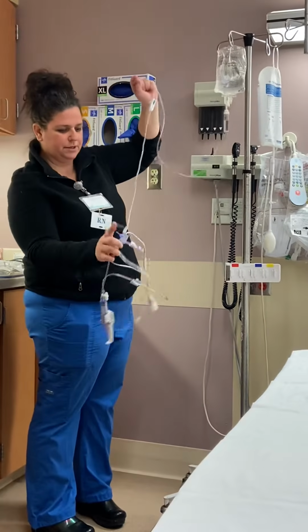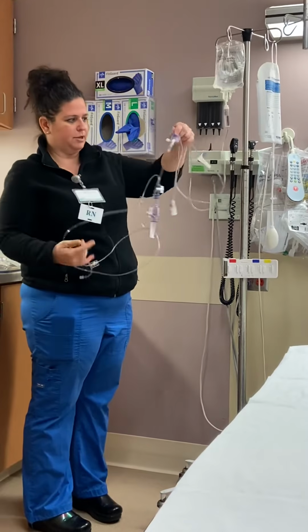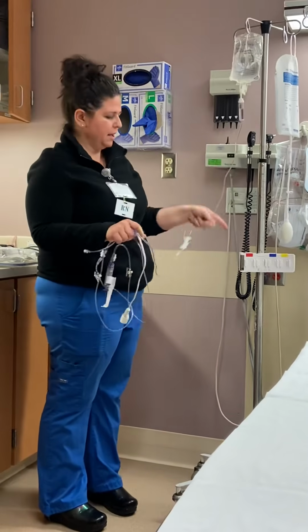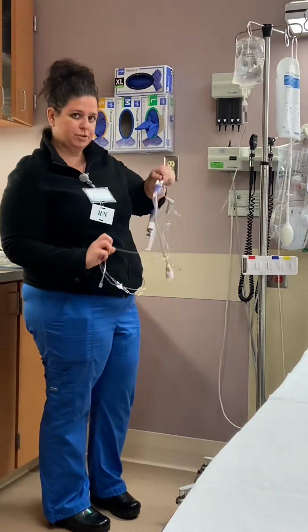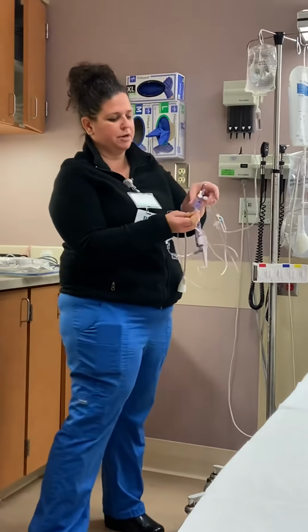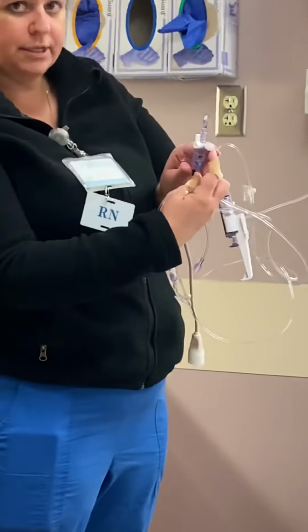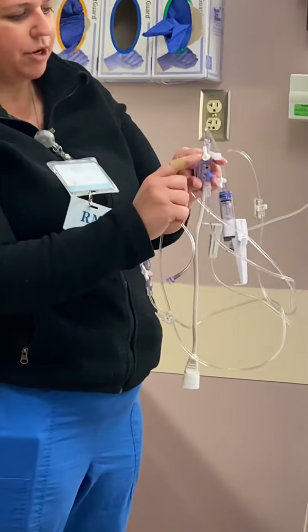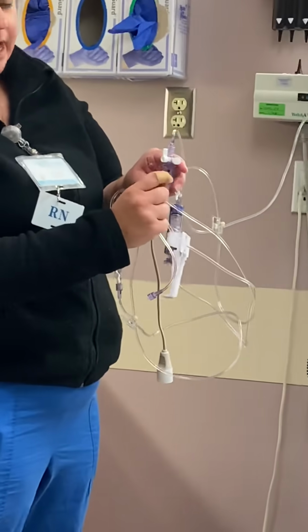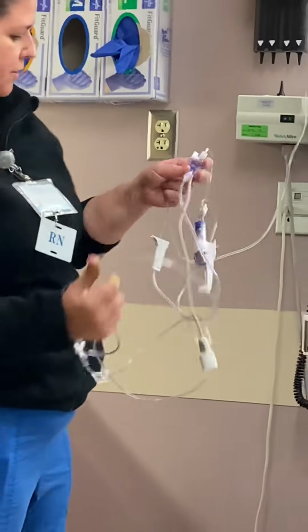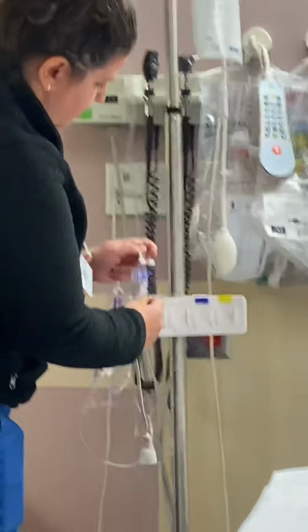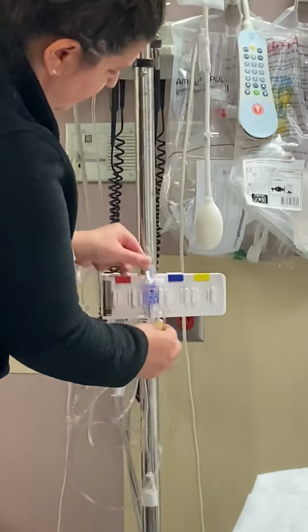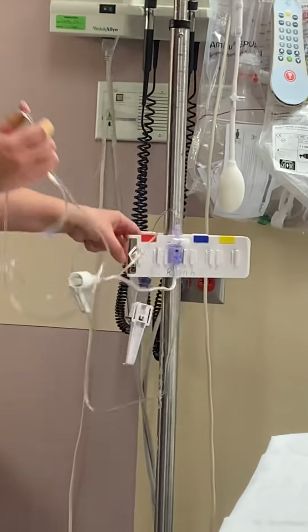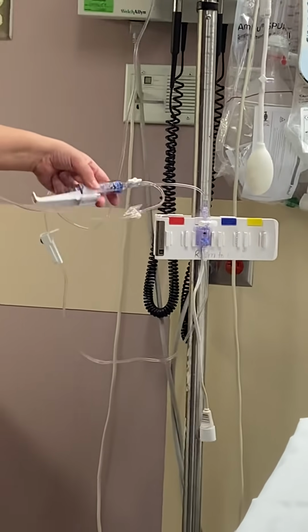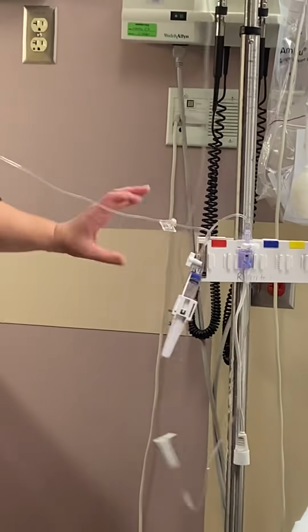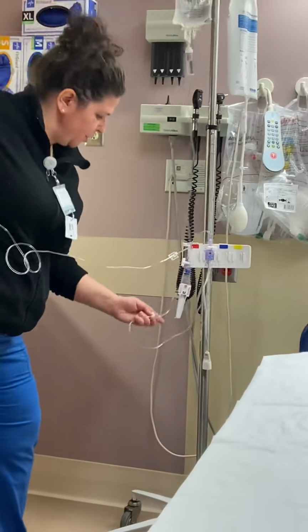And then what I need to do now is I need to get the transducer itself connected to my transducer holder. So on the transducer, you're going to have a port. This is your 0 port, and then you're going to have a valve, and you're going to have the pigtail.